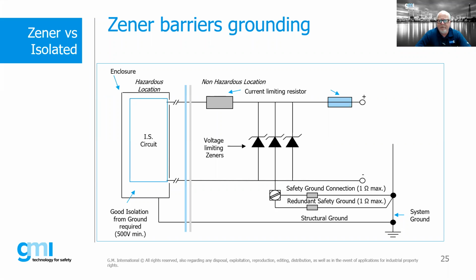But what we do not want is all the noise and all of the potential voltage spikes, everything else that could be existing on structural ground, to come into that safety ground. Notice that our requirement, and this is true whether you're following IEC standards or North American standards or standards around the world, is the same. We want 1 ohm of resistance or less for our safety ground. Sometimes people will ask, how big does that ground conductor need to be? It could be 4 millimeters squared, it could be 16 millimeters squared. It really just depends on whether or not we achieve 1 ohm resistance or less for our safety ground.